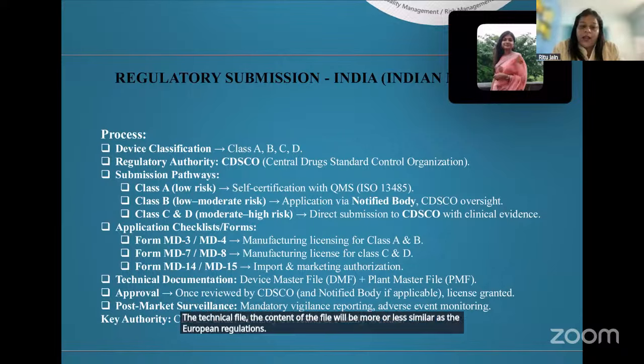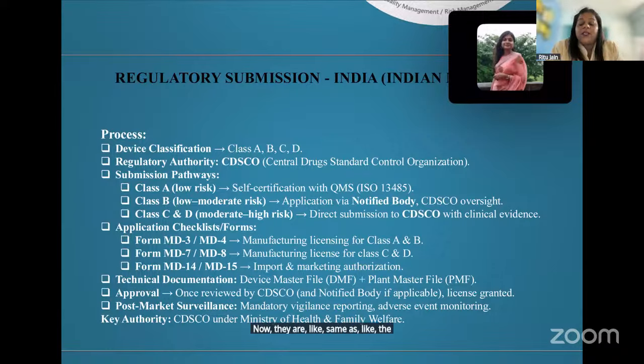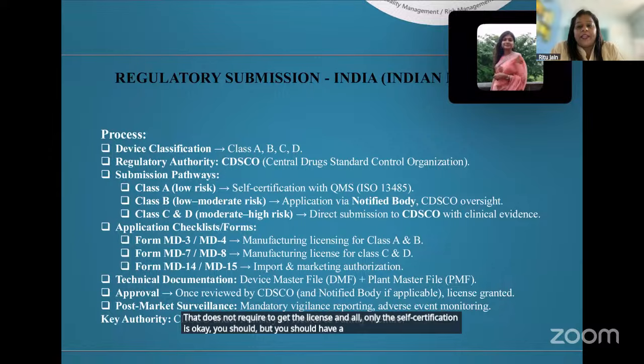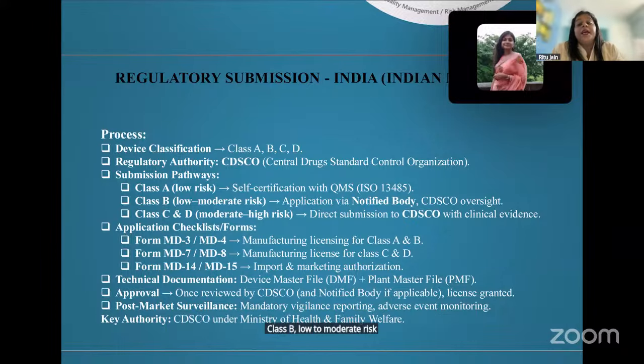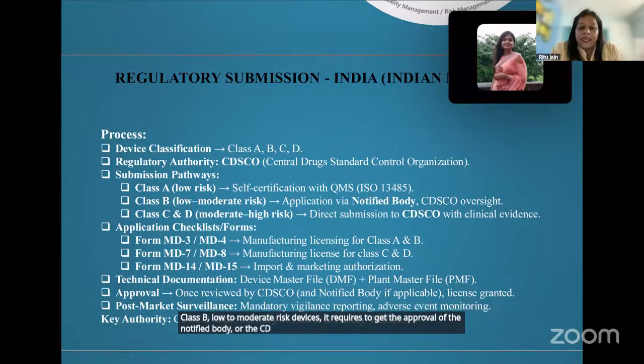For low risk devices, the class A devices, which are non-sterile and non-measuring, there is no requirement to get a license. Only self certification is okay, but you should have a QMS, a quality management certificate, which is the ISO 13485 approval. Class B, low to moderate risk devices, require the approval of the notified body or CDSCO oversight. Class C and Class D, moderate to high risk devices, require direct submission to CDSCO with the clinical evidence.